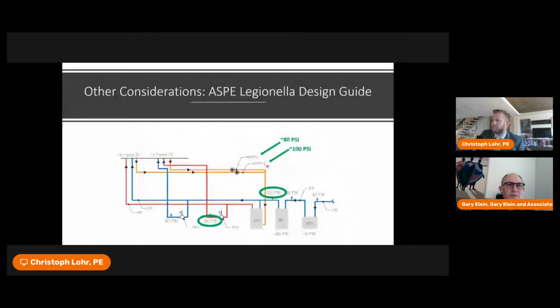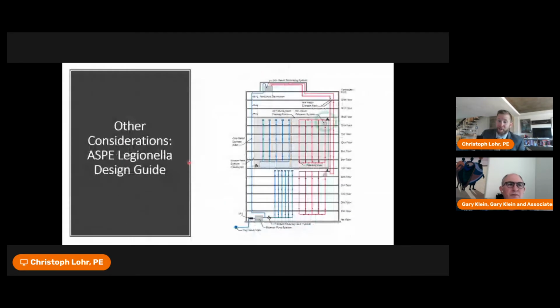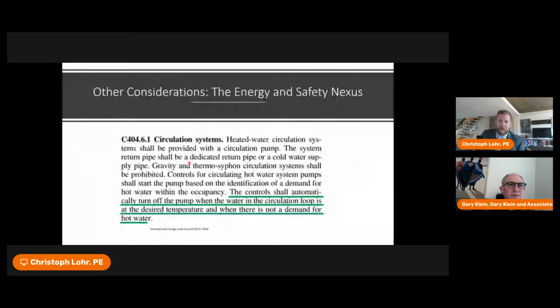In the previous case here, by combining two pressure zones, you had 80 pounds on hot water return pump 1, and you had 100 pounds on hot water return pump 2. In essence, you've created a dead leg in hot water return pump 1. And trying to do this through pump controls gets very, very tricky. And anytime you add complexity to a system, the likelihood for failure increases, which is why it's typically not recommended.